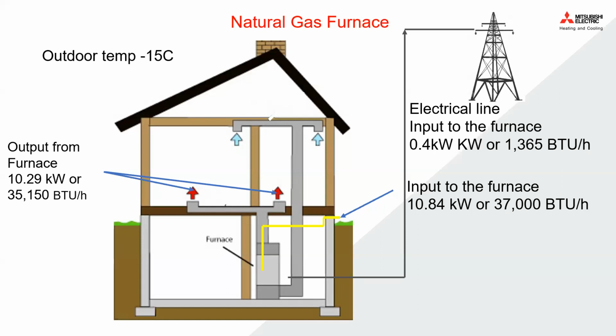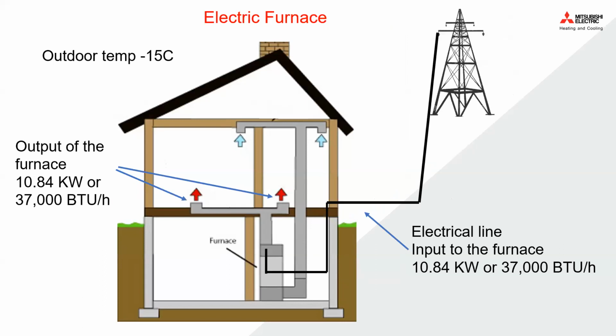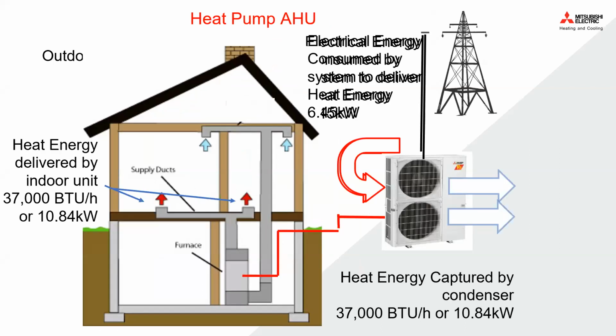So here's an image of a condensing furnace, 95% efficient. Obviously, it can never be 100% efficient, as there will be losses. When you take into account the electrical consumption, it now drops down to 91%. In this image, we have the same home with an electric furnace, and we'll essentially call it 100% efficient. So 10.84 kilowatts in, 10.84 kilowatts out.